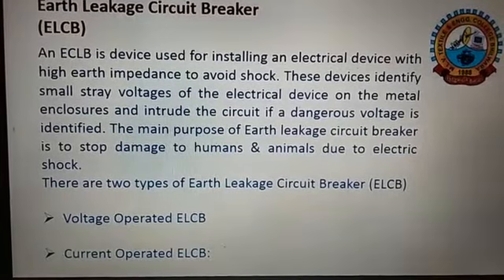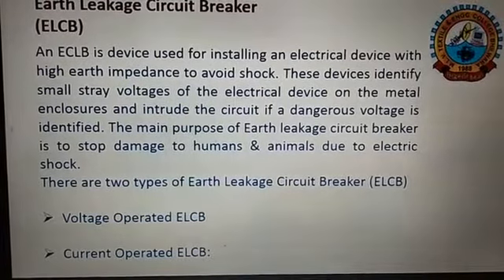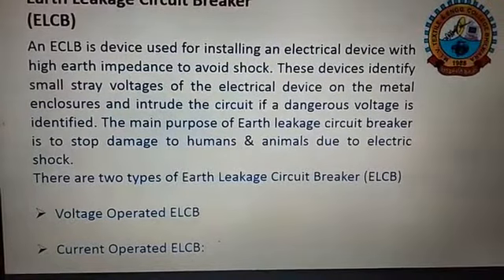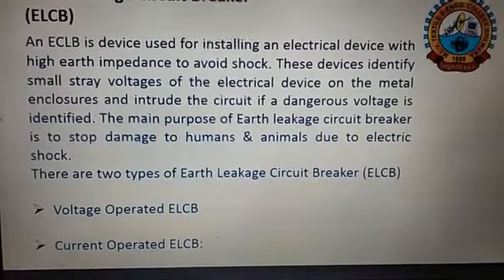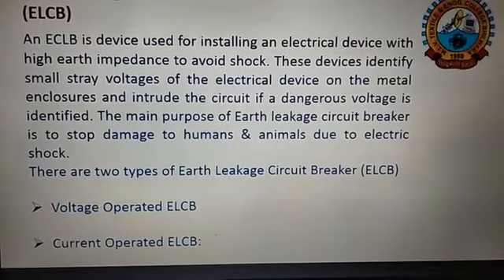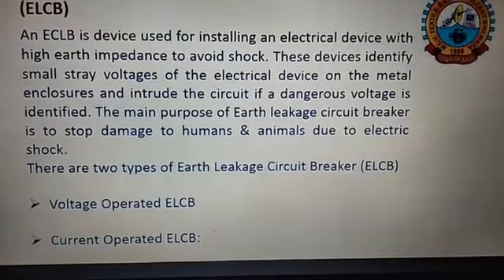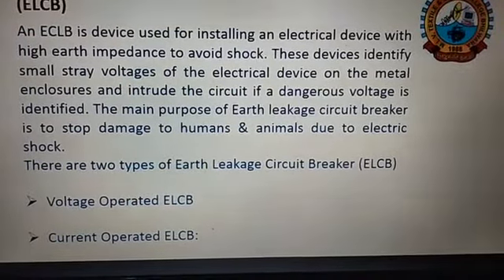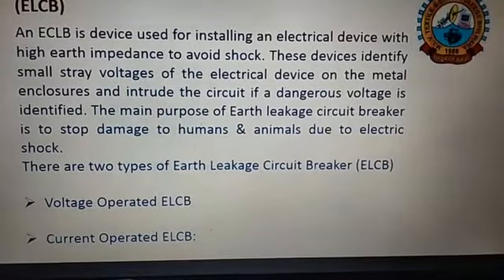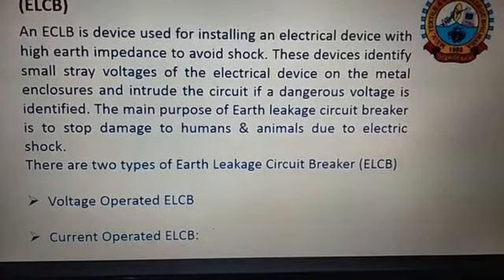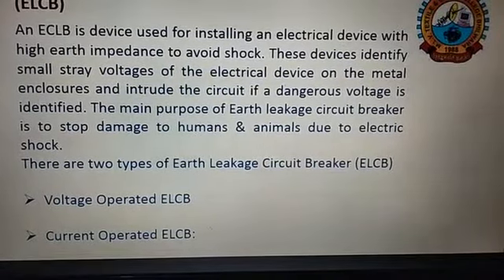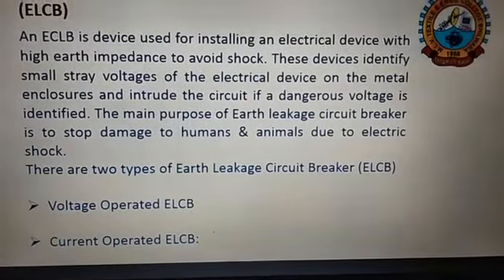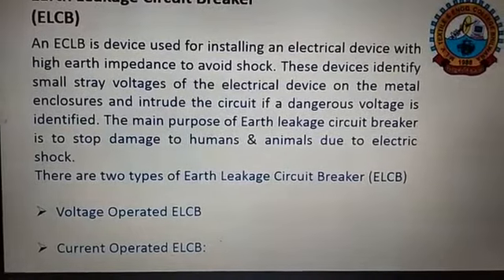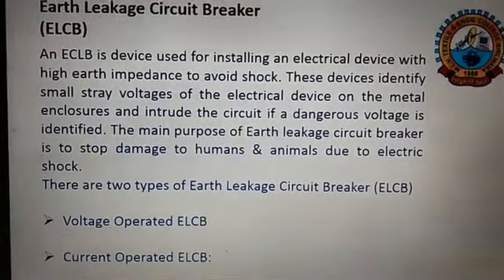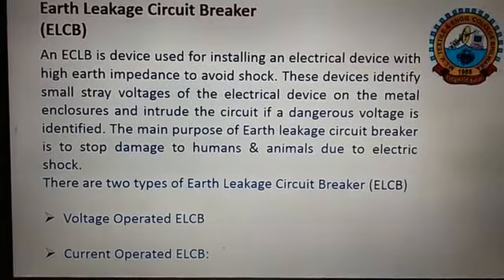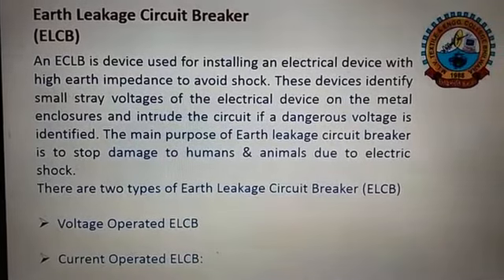An ELCB is a device used for installing an electrical device with high earth impedance to avoid shock. These devices identify small stray voltages of the electrical device on the metal enclosures and interrupt the circuit if a dangerous voltage is identified. So it has a capability to identify the unwanted voltage. The rating of ELCB is different for different types of equipment.